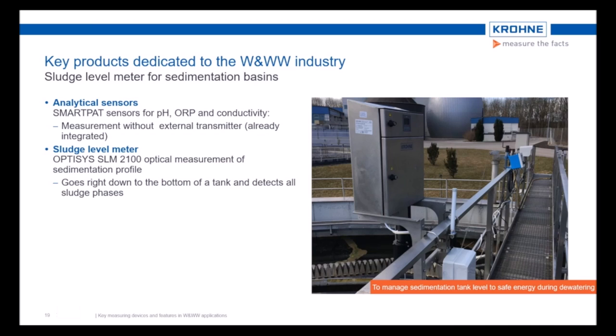The suspended solids concentration is measured using transmitted infrared light, which delivers precise measurements regardless of sludge color changes. The medium to be measured is penetrated by a beam of light in the measuring gap of the sensor. The suspended solids and sludge particles absorb or reflect the light and thus weaken the intensity of the beam. So the attenuation of energy between the light source side and the receiver side of the measuring gap correlates directly to the level of concentration of particles, which can then be easily calculated.